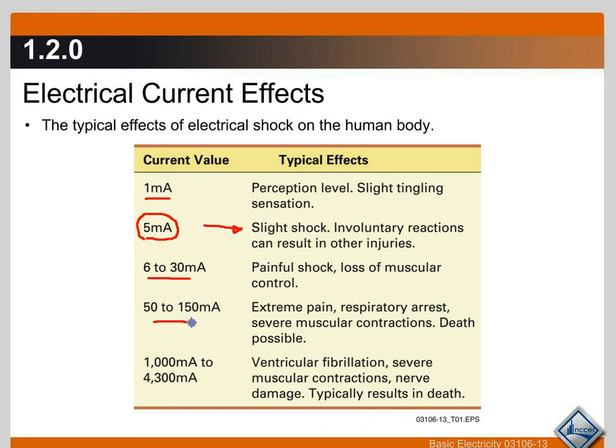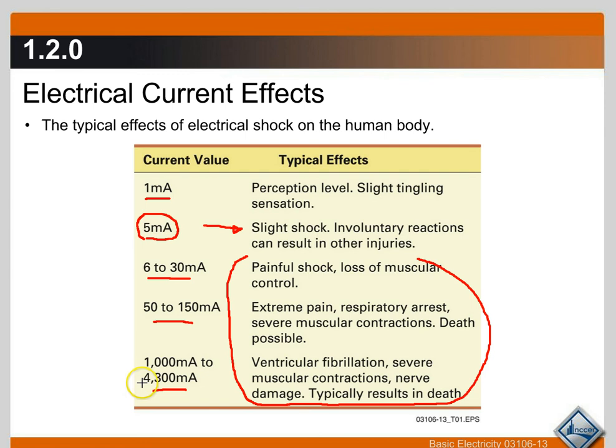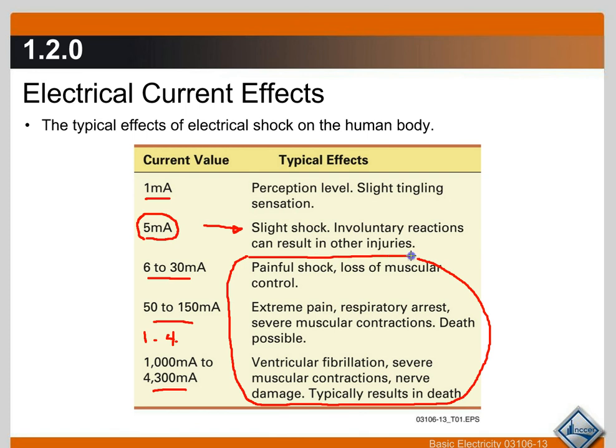I myself have never experienced those lower ranges, but this is where you want to stay away from. When it says 1,000 milliamps and 4,300 milliamps, we're only looking at 1 amp to 4.3 amps. Most of the equipment we work on has circuit breakers that don't pop until you hit 15,000 milliamps or 20,000 milliamps or more. The higher the voltage, the more chances of you ending up in that dangerous range. When you're in the 480-volt range and above, that's not going to cause a slight shock and jerking your hand out — in big commercial systems, that's the range you're going to be in.